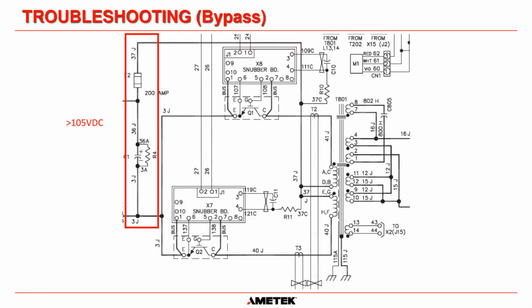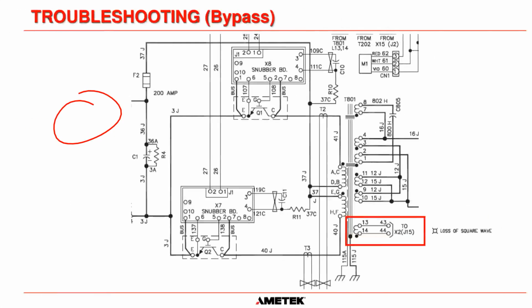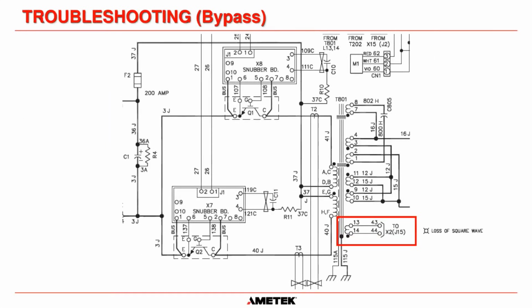If the system has transferred to bypass, then the system is always going to transfer to bypass if the inverter fails. So you should always check if you have 105 volts coming in, because if you don't, the inverter is going to shut down because of the B1 input breaker tripping, and it will transfer to bypass. So first thing you should do if it's transferred to bypass is check if you have 105 volts going in. Okay.